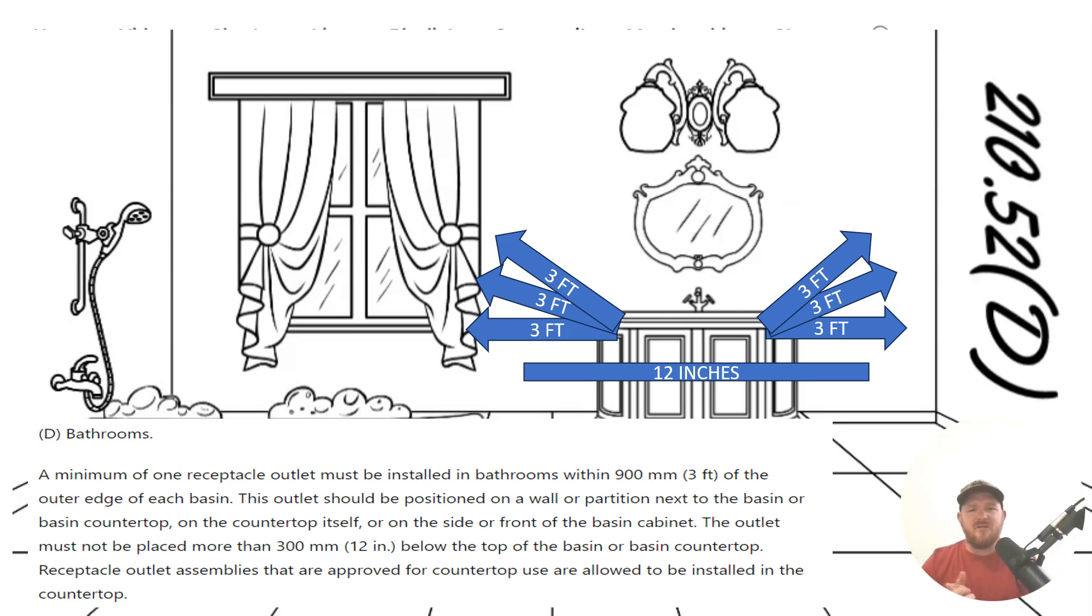It says receptacle outlet assemblies that are approved for countertop use are allowed to be physically installed in the countertop, like a pop-up or something like that. Now you have to be careful with this last part here. There are two different major types of listings for these receptacles that are in like the pop-up receptacles. There are some that are listed for work surfaces and there are some that are listed for countertops.